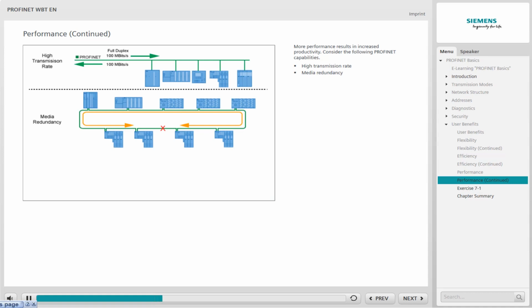PROFINET implements redundant structures without additional switches. The redundant setup considerably increases the plant and machine availability because the failure of individual devices does not affect communication. Media redundancy is integrated in PROFINET and can easily be utilized without added costs. In case of network interference, it is possible to quickly perform network diagnostics, which greatly accelerates troubleshooting.